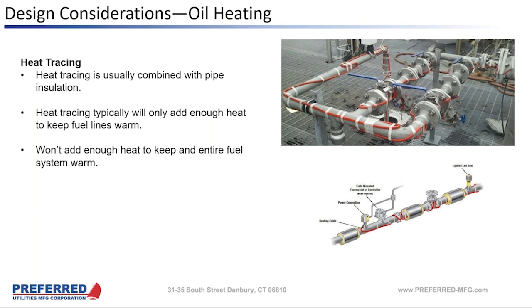So we get asked a lot about heat tracing. I found this picture of a plant that was being built out in West Texas, where it can get very cold too. And this was during construction. You can see that the heat tracing cable is being held in there with strapping tape, and then it's going to be covered by insulation. It's really only effective with insulation. If you just left the heat tracing out there, most of the heat that you're adding to the system is going to go right into the air. But after you insulate that pipe, then the heat that you're putting into the pipe will actually get to the pipe and get to the fuel.